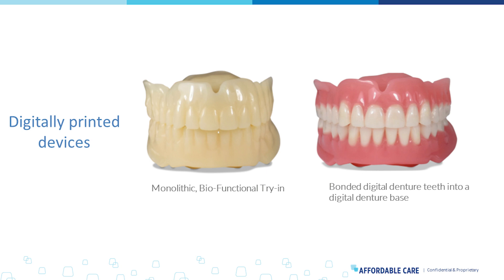There's a big difference in regulatory qualifications between try-ins and final dentures, and we have to give Keystone a lot of credit for their regulatory prowess in making sure we have safe, validated materials. For a try-in denture, it is technically a class one device — minimal contact in the oral cavity, not meant to be long-term. For definitive devices we need more robust clearances: a class two device would be a final denture, requiring individual clearances for both denture base and denture tooth, as well as validation of bond strength as a system so teeth aren't popping out.